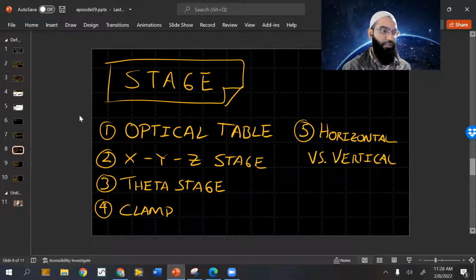Now let's talk about stages. All right, this is actually quite important: how you align and get your transducer in view. Because the z-axis, or the axis in plane of your camera, is quite important because that's how you get your focus image. And the rest of it is to maneuver your device to view the right portion. You're honestly going to be looking at the tip of the transducer, which has the most displacement, so you can get the highest amplitude and the best measurement. So there's a couple of things to think about there.